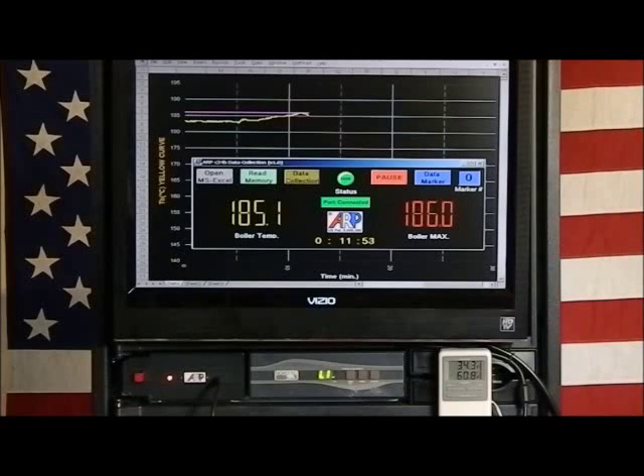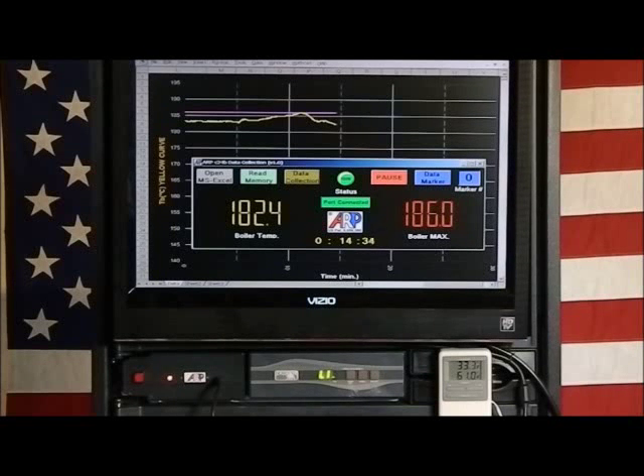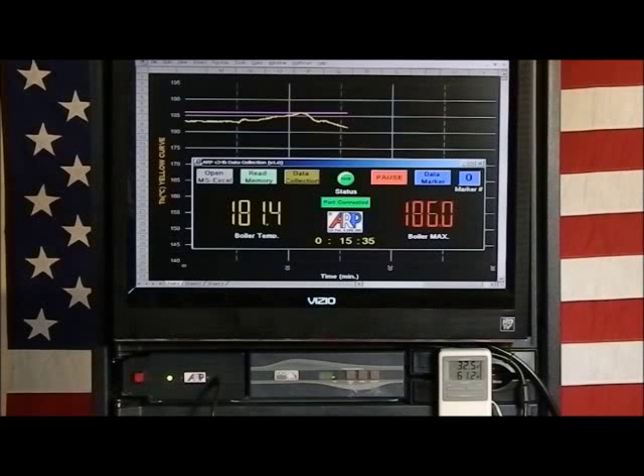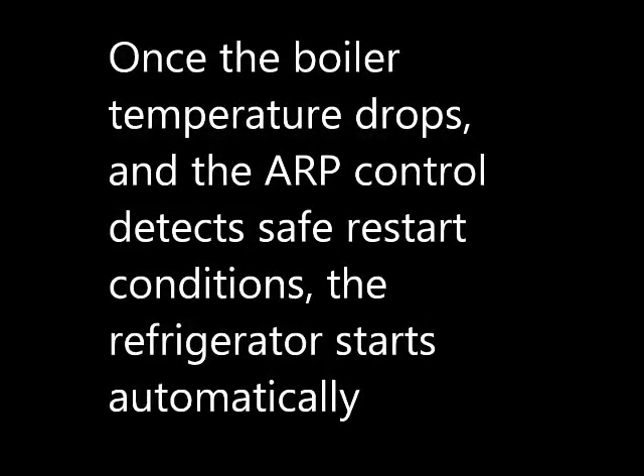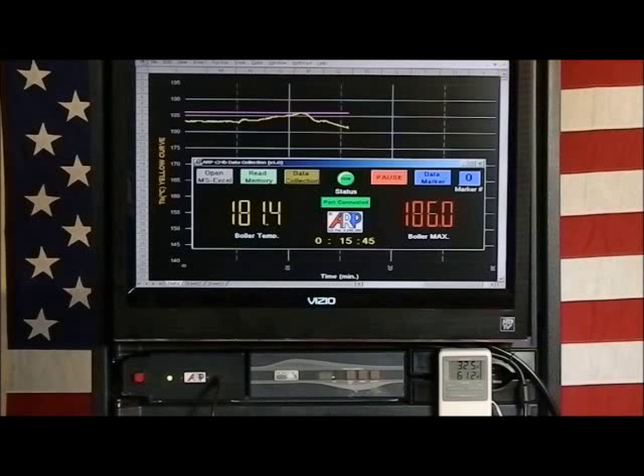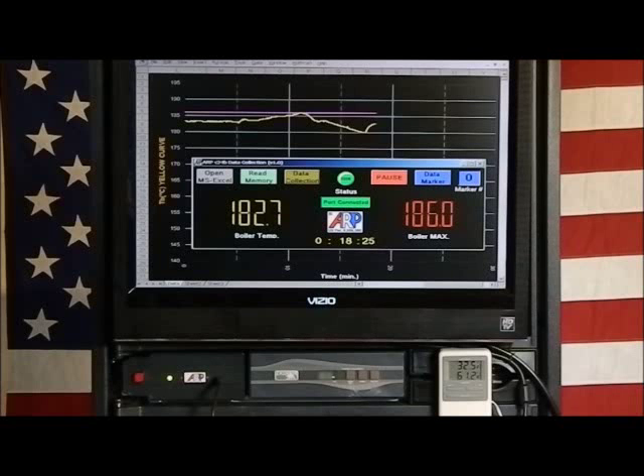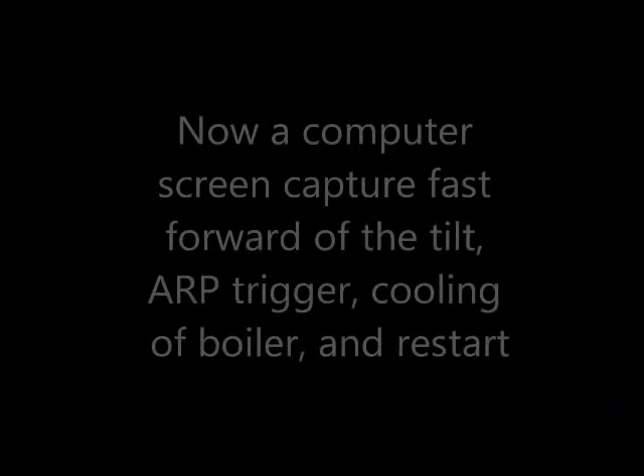With the unit leveled, the ammonia will return to the holding tank. Note that with the unit leveled and the heater off, the temperature rapidly goes down in the boiler. The ARP control will determine when a safe time to restart the heat source is. Once the boiler temperature drops and the ARP control detects safe restart conditions, the refrigerator starts automatically. Note that the flashing red LED turns to a flashing green LED to inform the operator that a trigger event has occurred.